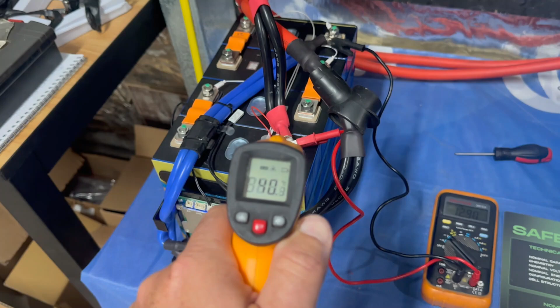Quick thermal test on the terminals: 40 degrees, 42, 39. None of that worries me, that's all perfectly normal. BMS, 24 - it's not even warming up.